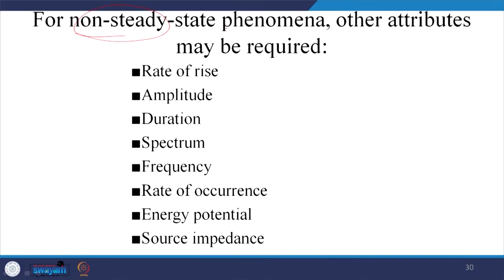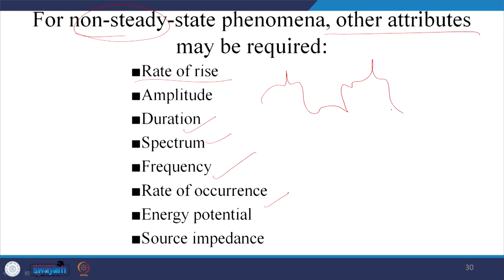For non-steady-state phenomena, other attributes apply to transients: rate of rise (e.g., when charging a capacitor), amplitude, duration, spectrum, frequency, rate of occurrence (such as a notch edge every 5 cycles), and energy potential — how much energy is associated with the transient. A very high voltage spike of short duration may have low energy potential. Source impedance also plays an important role in the rise time of these events.